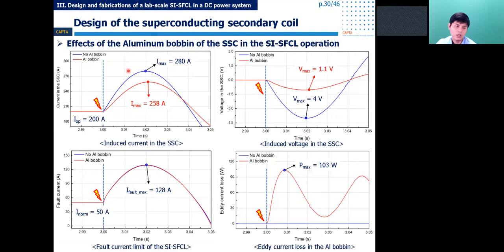So as you see in the simulation result like this, using the aluminum bobbin, the induced voltage and the induced current were greatly reduced during the fault. Because there was induced current in the bobbin, it caused eddy current loss like this. In addition, the aluminum bobbin didn't affect the fault limit capability of the SFCL, as shown in this graph.